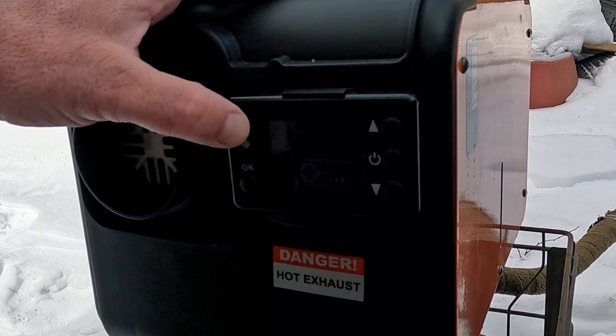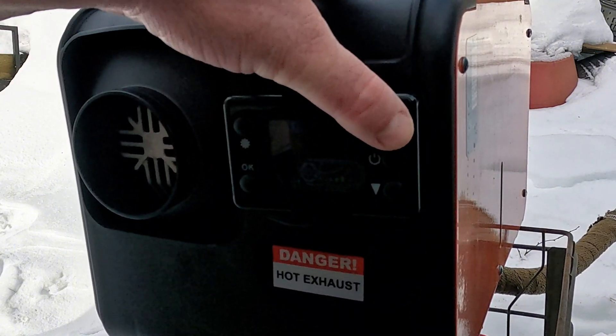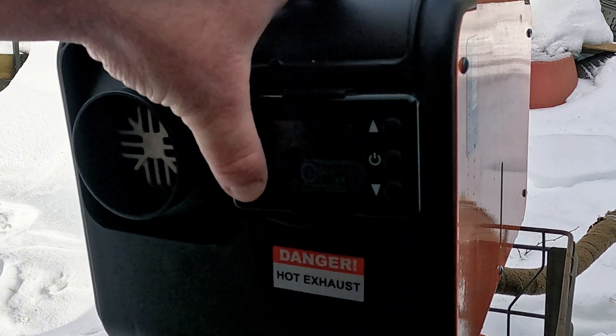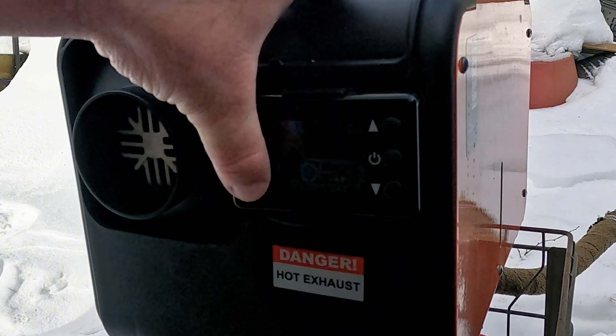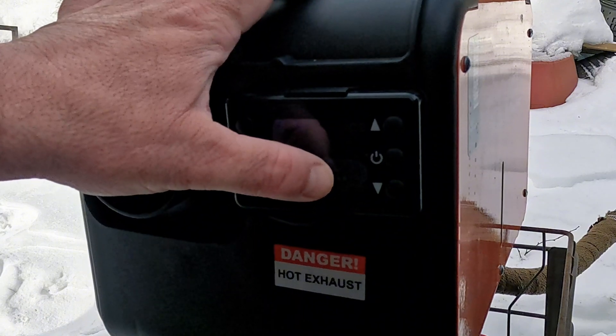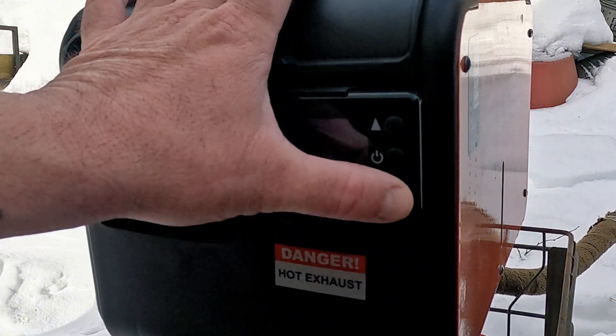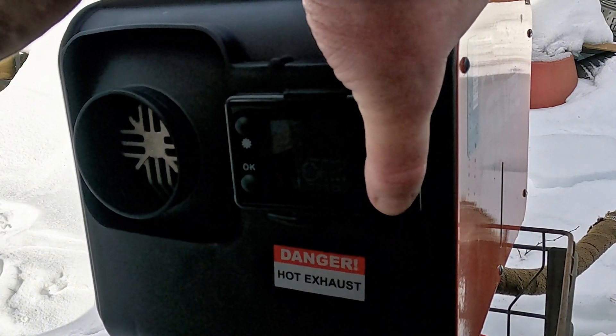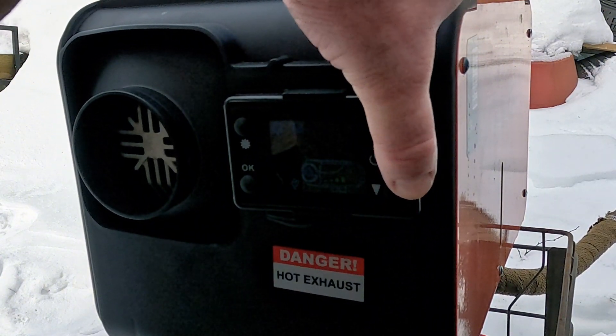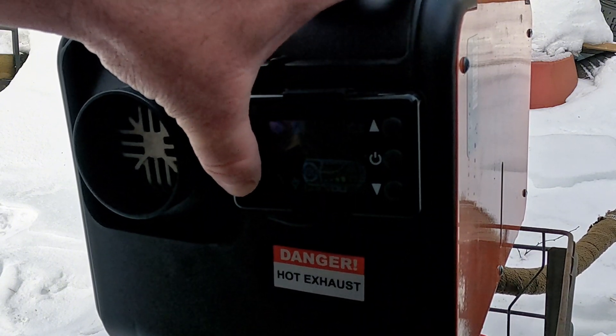To get into your settings, press the gear button repeatedly until you get four lines, then enter the code: 1, 6, 8, 8. That brings you to the low setting — we'll leave that for now. The high hertz shows 5.3; I'm going to drop that down to 4.5 and see what happens, since 212 ppm was far too high. We'll adjust up or down from 4.5 from there.